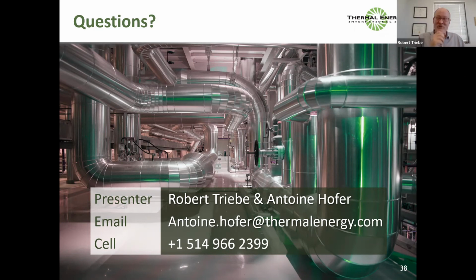It's a good question, Andrew, and because we come from somewhat different backgrounds, like the 20 and 30-year scale, we often are looking at the 5 and 10-year scale. So the short answer is no, but it would come out. I don't know what kind of lifetimes you guys carry for condensing boilers. I'd be surprised if it's past 15 years. Whereas with a hydronic boiler, you could carry 30 and then look at the economics about changing out the tubes in the economizer. It would be a bigger winner in the longer term scenario.